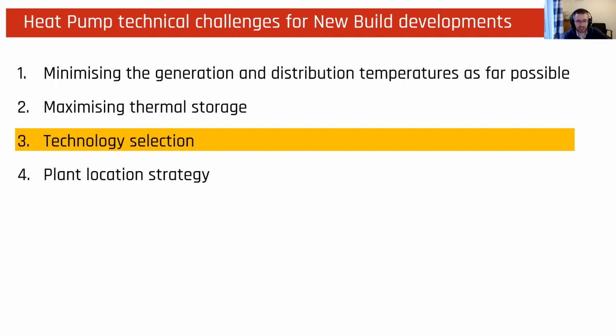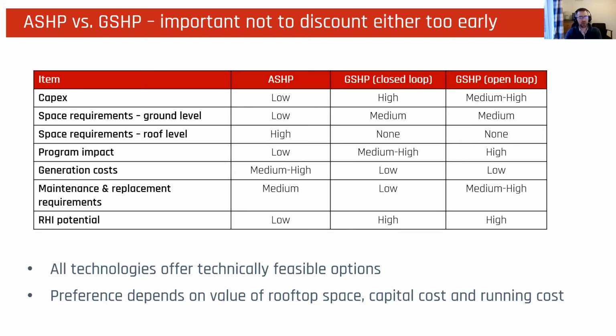In terms of technology selection, my experience, and in general, is that air source heat pump is the de facto starting point, particularly when you get into the site-specific challenges around rooftop space. Where are we going to locate those heat pumps? Do we have enough space? I've got a very, very tall development, so I can't locate the whole plant room on the roof. So I've got to go from the air source to ground and then back up again, and it starts to become maybe quite inefficient.